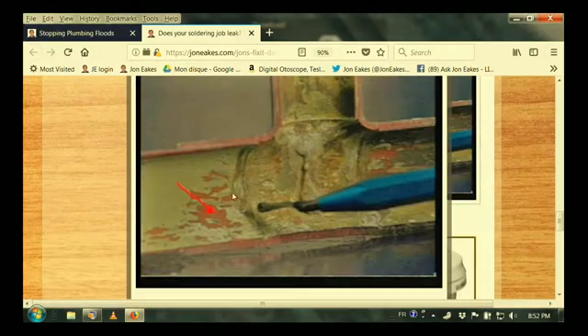You're always told when you're doing plumbing that you take off the rough edge on the outside, but you also take off the rough edge on the inside. And so many people don't do it because it doesn't get in the way. Why should I bother? This is why you bother. The turbulence caused by water, particularly if it has minerals in it, actually comes here, jumps over and hits the wall, and this wall can actually wear totally through and the joint leak a few years later because you didn't take the burr off. You had a perfect solder job, but you didn't take the burr off. So we have these strange things we learn as we try to solve problems there.